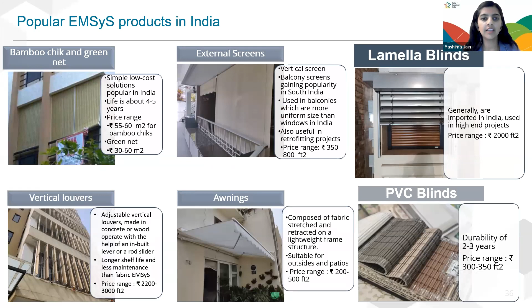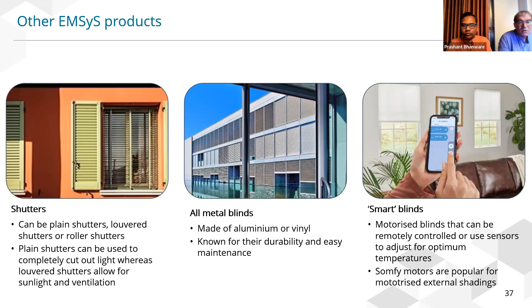Actually it's relatively simple. Whenever the solar radiation hits above, say, 100 watts per square meter per window, then you lower the blind. This is the logic in control, and it's also what people do normally. In the morning, when you no longer have natural ventilation with the window open, you close the window and lower the blind. At the same time there is no mass logic there - it's really just when the sun is hitting that you lower them, which doesn't make much sense.